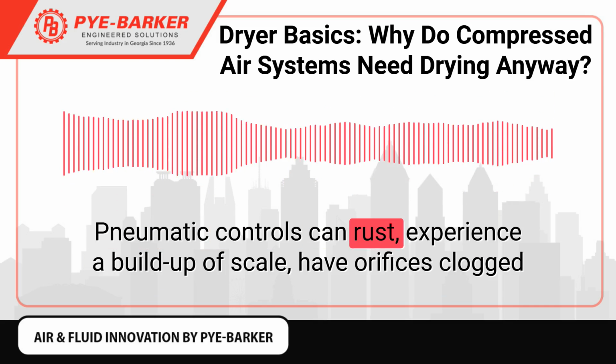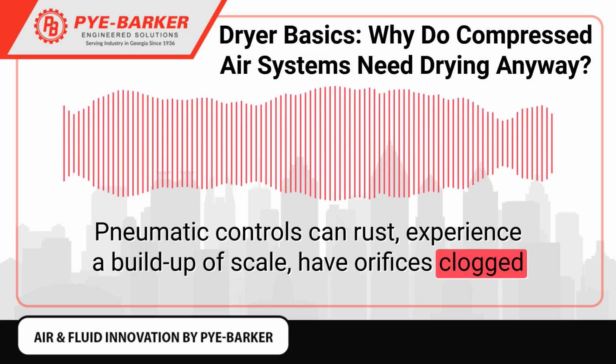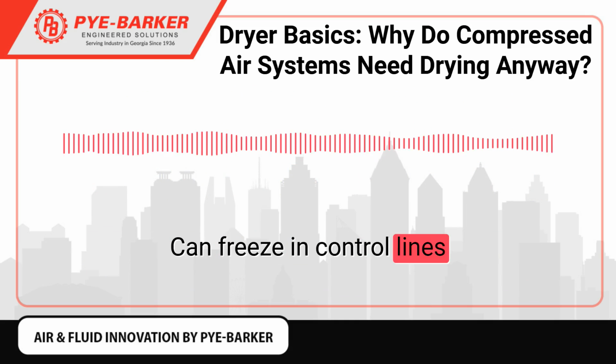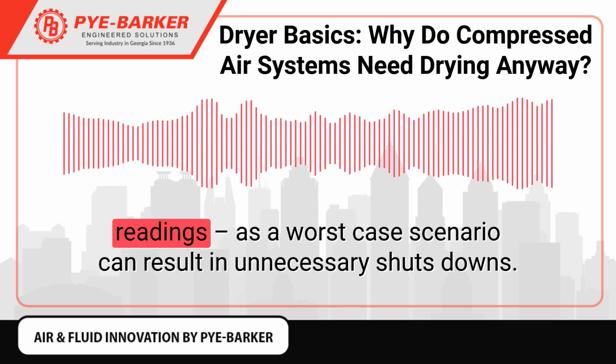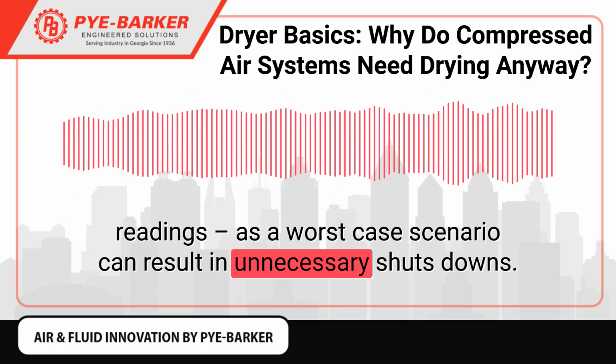Pneumatic controls can rust, experience a buildup of scale, have orifices clogged resulting in product damage or shutdowns, can freeze in control lines, and cause corrosion of air or gas-operated instruments, giving false readings. As a worst-case scenario, it can result in unnecessary shutdowns.